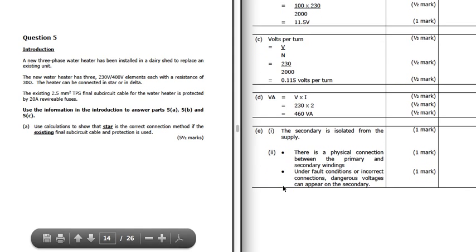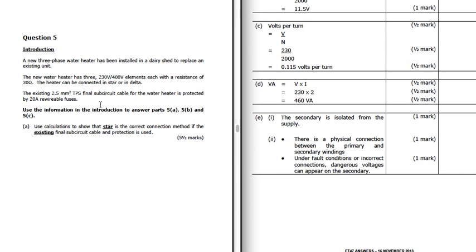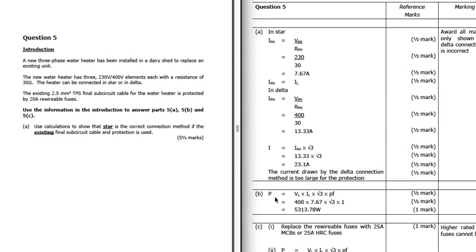Question 5, we've got a new 3-phase water heater in a dairy shed. We've got 3 230 volt 400 volt elements, each with a resistance of 30 ohms. The heater can be connected in star or in delta. So these elements can run at either 230 volts or 400 volts. We've got 2.5 mil TPS, and we've got a 20 amp rewirable fuse. And we're going to use calculations to show that star is the correct connection if the existing final sub-circuit cable and protection is used. So if we're going to use a 20 amp rewirable fuse, then we've got to make sure that the current that flows into that heater is less than 20 amp.